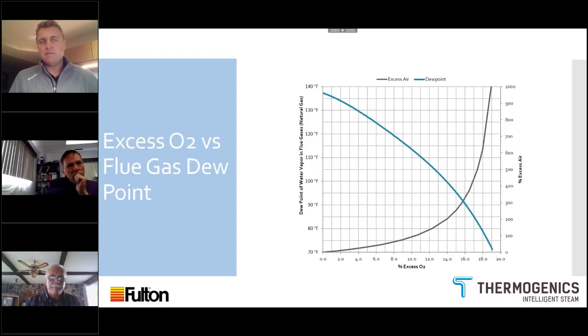The number of hospitals that have played with reducing their steam pressure and run into three to four times a year very expensive valve replacements and potential downtime issues has been staggering for us. And so while I think there's room for a 10 to 30 PSI drop in many hospitals out there, be very, very careful to not just randomly drop 50 PSI because that's just what one of your users can get away with. There are going to be system issues that occur from that, and those maintenance problems will cause you headaches and money to offset the savings of that fuel.